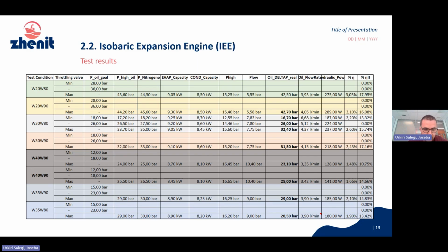As you see here, apart from the conditions that were expected, we also tested the water 35, water 90 condition. Why? When we started testing with 40 degrees of water supply in the condenser, we realized the feed pump did strange things, for example strange noises, and we didn't like these noises. So we decided to be conservative and said, okay, the feed pump doesn't feel very comfortable in these conditions, and maybe it's better not to force anything and test in better conditions.